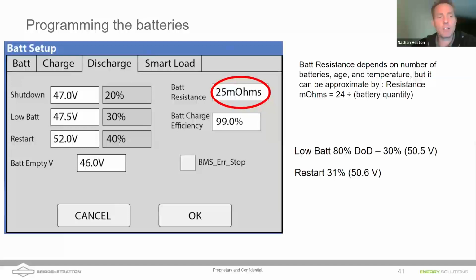The shutdown voltage there is when that inverter will do a shutdown. That will shut off the batteries and switch over to different sources. The low battery voltage is really just a voltage, or a percentage, that triggers the warning symbol. And then the restart is when you've gone past the low battery cutout so that the inverter is shut off from the battery. It's going to initiate a new charge cycle, and it won't start discharging the batteries again until you hit that restart voltage. The battery empty voltage that you see on the screen is there to protect the inverter from having the battery shut itself down at the BMS, the battery management system within the battery. So I know I'm pretty short on time. I'm going to keep moving, but again, make sure you get that battery resistance right. And I've shown you on the screen what values to put in for the battery resistance.